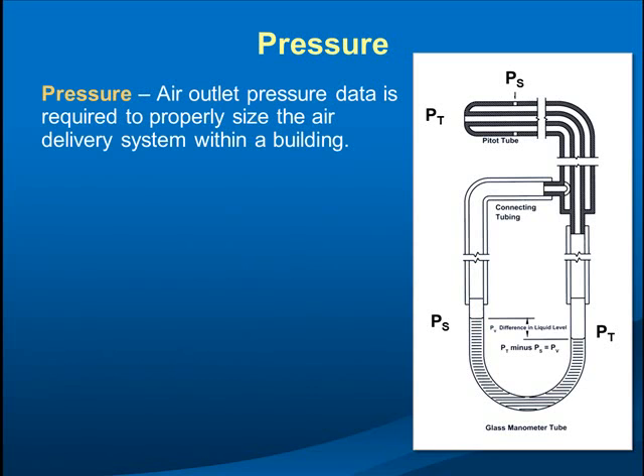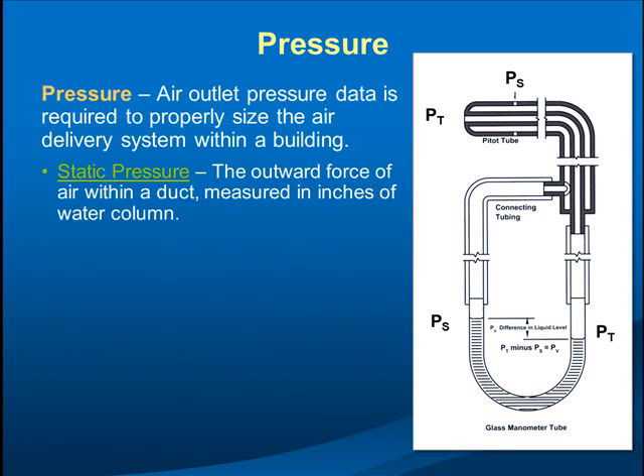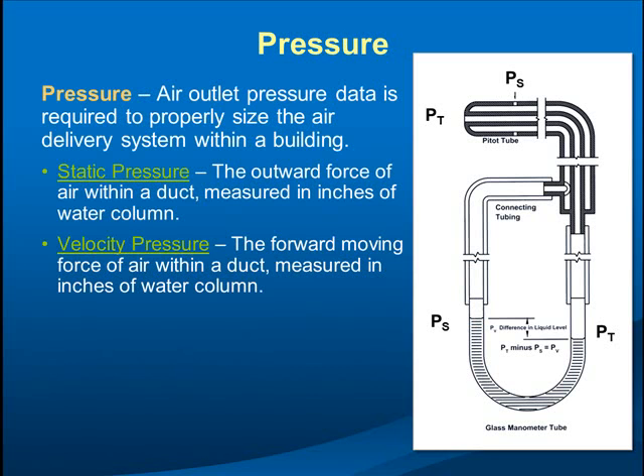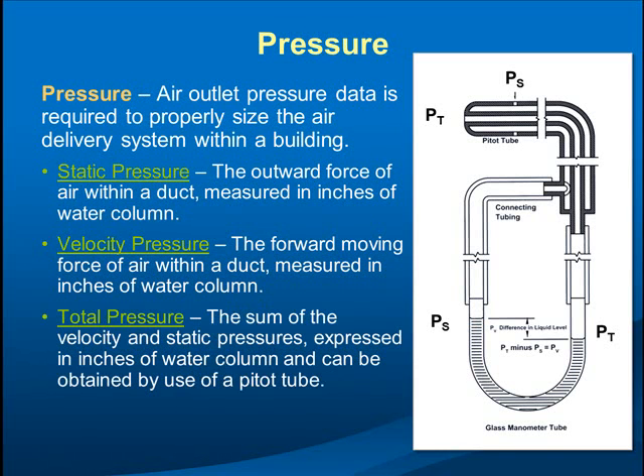We need air outlet pressure data to size the fan and ensure enough pressure reaches the diffuser at full airflow to deliver the required cooling. Static pressure is the outward force of air within the duct; velocity pressure is the forward-moving force; and total pressure is the sum of the two. The equation is: p_t = p_v + p_s. Most people today design with static pressure, but theoretically you should use total pressure. You need enough static to get the air through the diffuser.